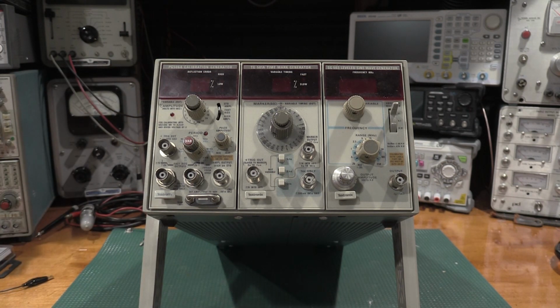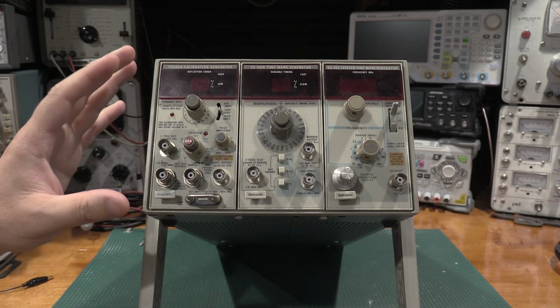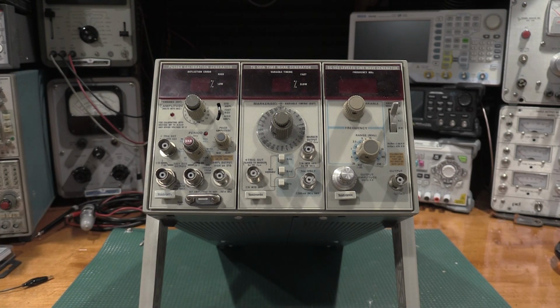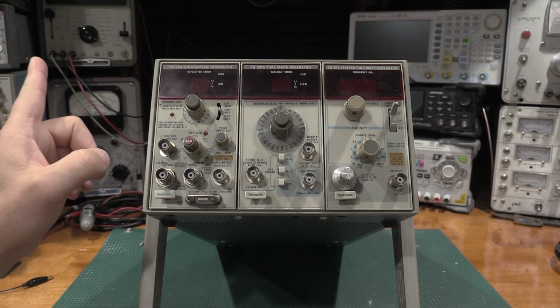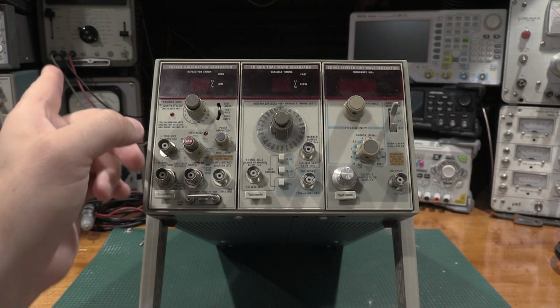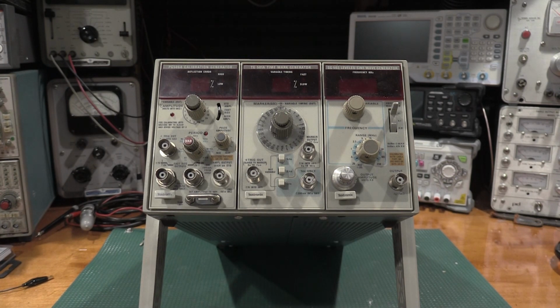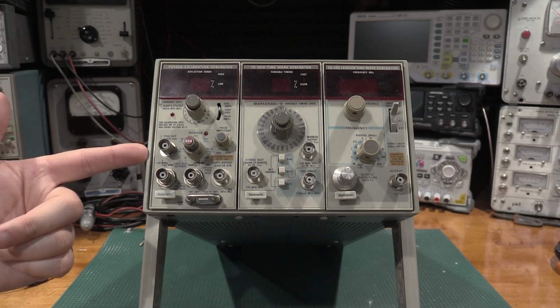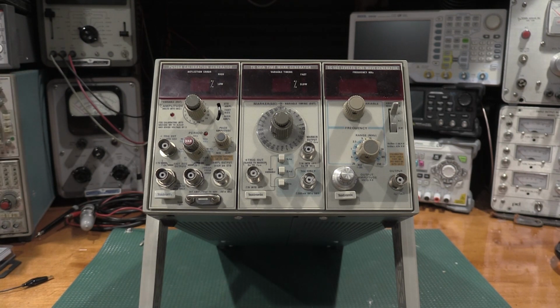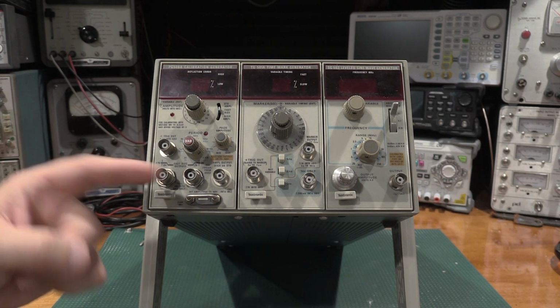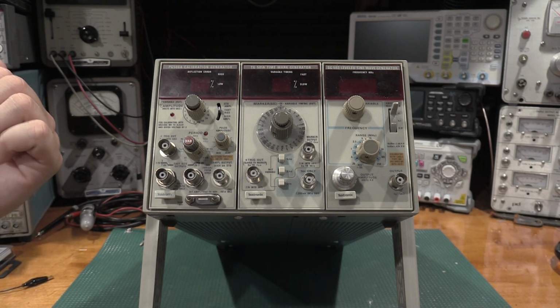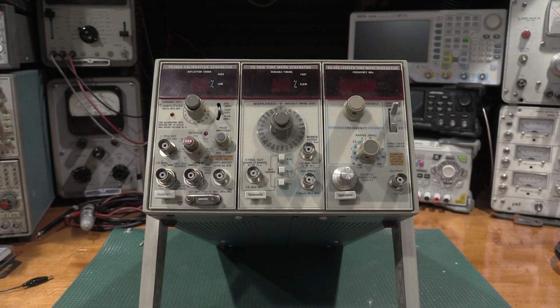If I remember the specification right, it's plus minus 0.025% is what I want to say. So you need a meter better than 0.025% to check it. Well, it has the same DC accuracy as my 6500 right there. So I can't use that to check it, because if it's off, is this off or is the 6500 off? And then you can get into tolerance stacking where this is off at its extreme end, the 6500 is off at the other extreme end. Now you have a wide gap but that gets into measurement uncertainty and a few other things.